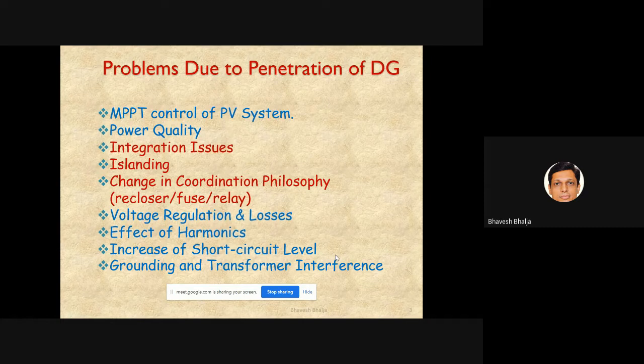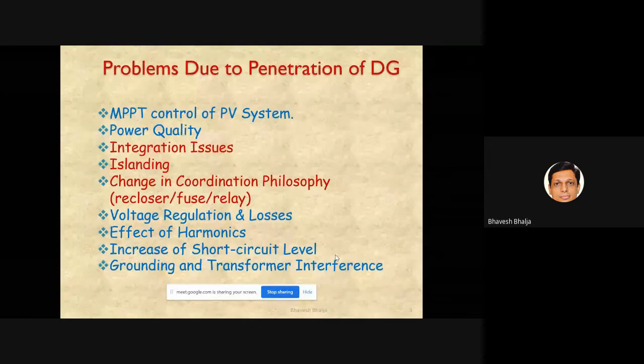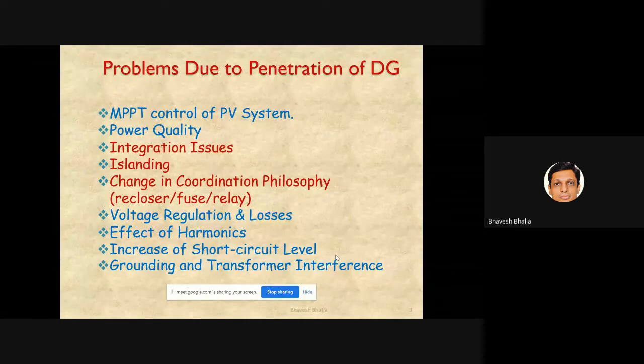So voltage regulation plays an important role at distribution level, right? Even losses are also now equally important at distribution level because of demand side management and some other issues which we are handling by the utility. So when you connect DG with the grid at different locations, there is a change in voltage regulation. Basically it increases and it may violate your distribution limit of plus or minus 5%. So then you need to do something so that it again comes within the prescribed limit, right?